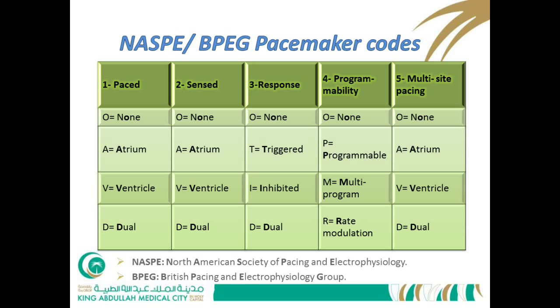For the first letter — chamber paced — it may be Atrium, Ventricle, or Dual: A, V, or D. The second letter — chamber sensed — is also A, V, or D. The third letter — response — may be Triggered or Inhibited. Inhibited means that if the pacemaker senses the myocardium's own electricity, it will be inhibited and not deliver a stimulus. Triggered means it will deliver a stimulus.